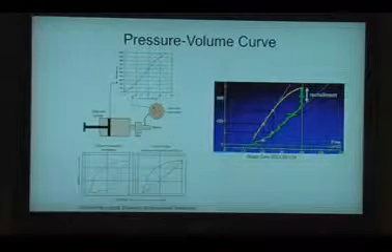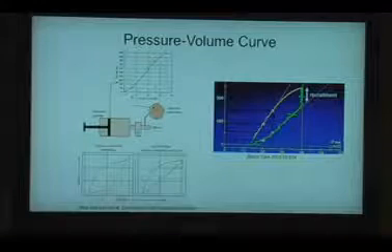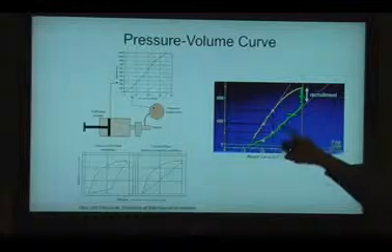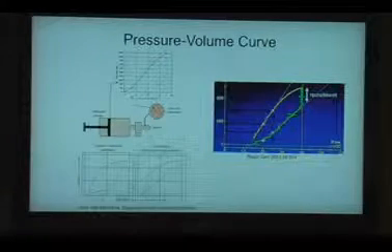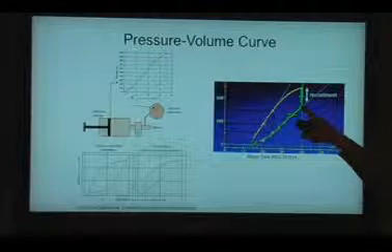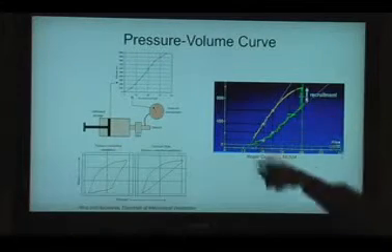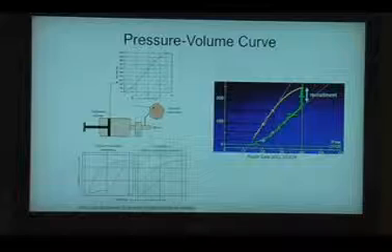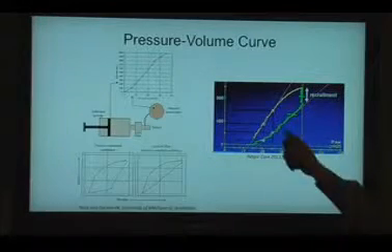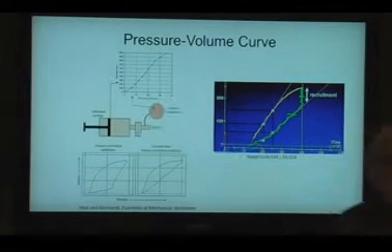It's almost like the syringe, pushing in more liters. With the PV curve function on the Hamilton ventilator, you can slowly inflate, hold the pressure, measure the amount of recruitment, and slowly deflate. And I have to say that I think the Hamilton ventilator does it correctly. I think this is a true PV curve, very similar to this one.